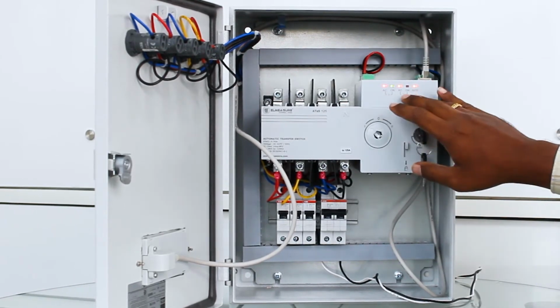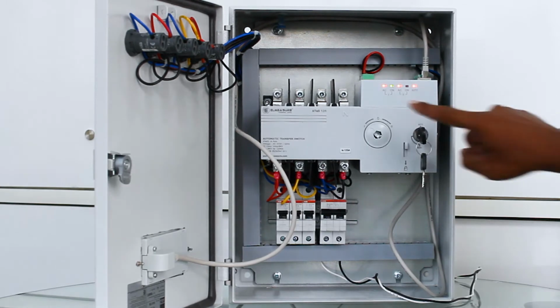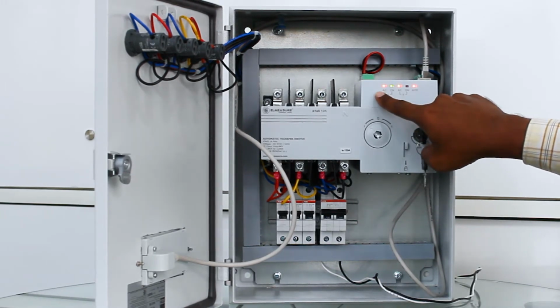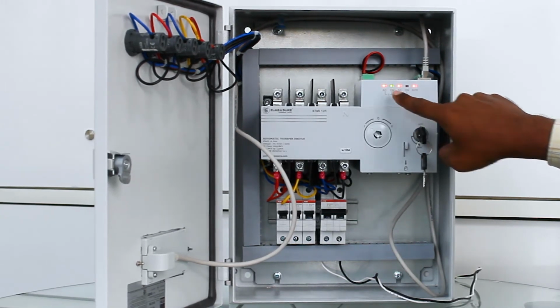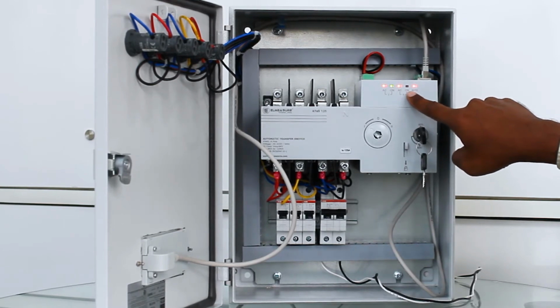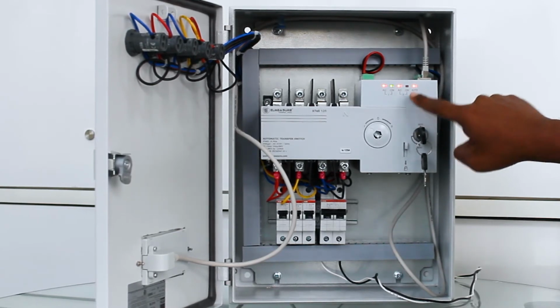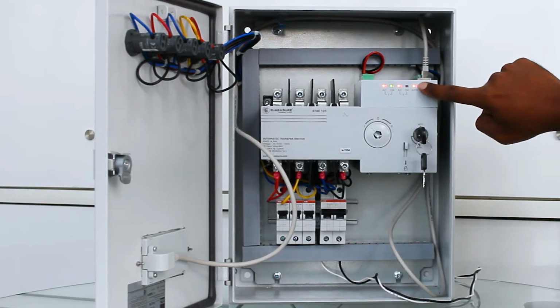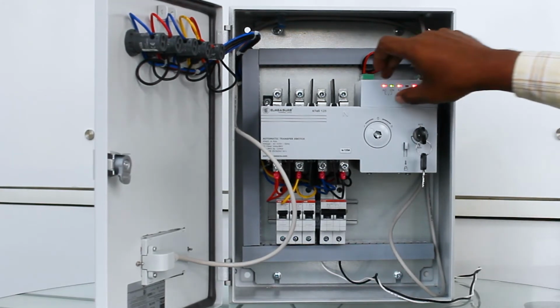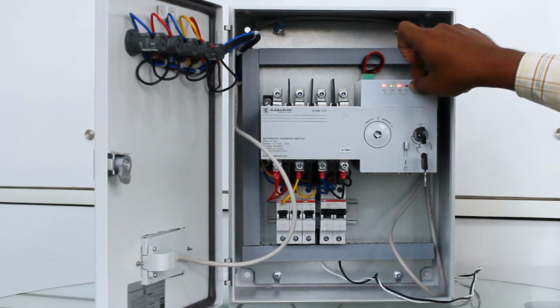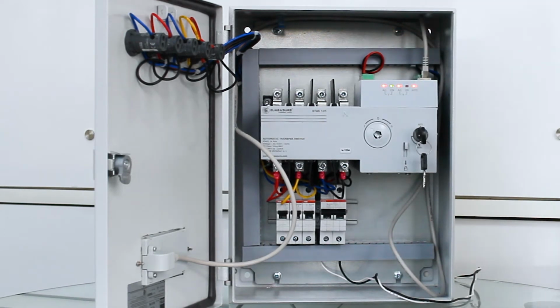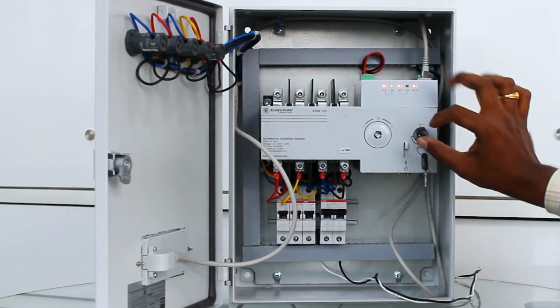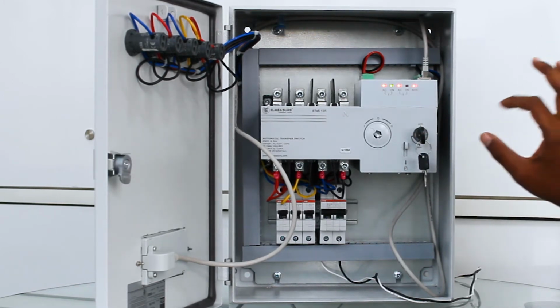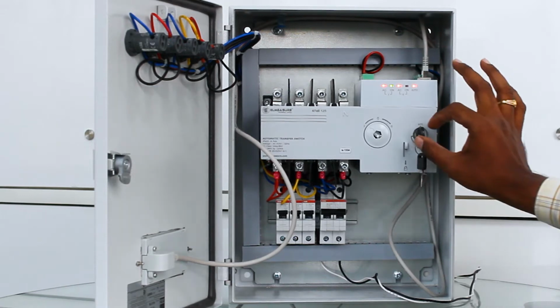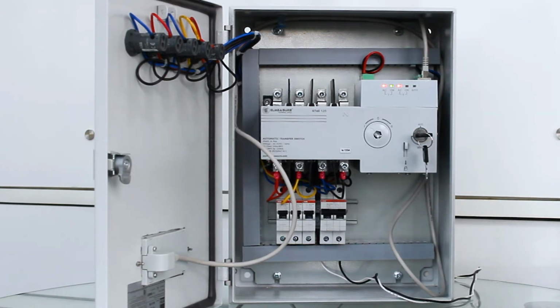Here we can see the 5 indications. The first 2 indications are for transformer healthy and load on, and the second 2 indications are for generator healthy and load on. And this is the indication for auto manual, and this is the controller part. Through this controller, during a mains failure, we can start and stop the generator also. And this is our auto manual key. Now it is in auto mode. If the customer wants to change to manual mode, we can do that.